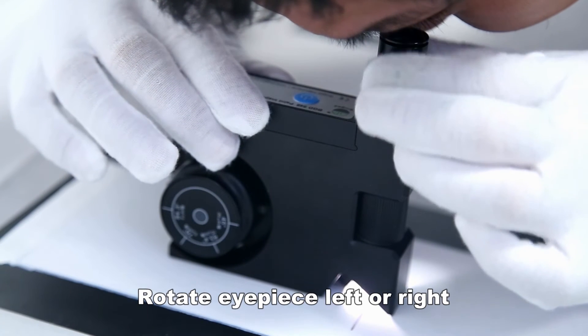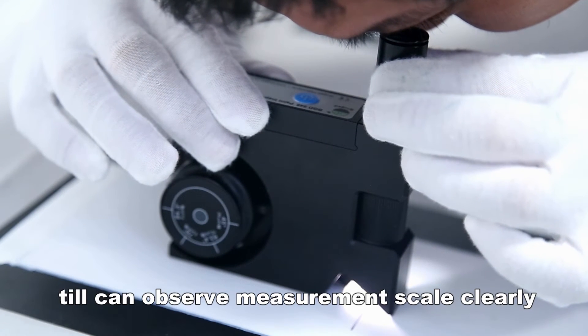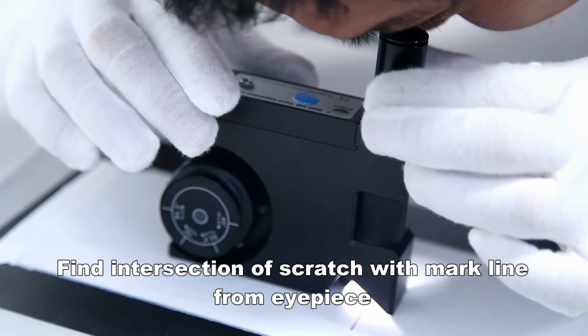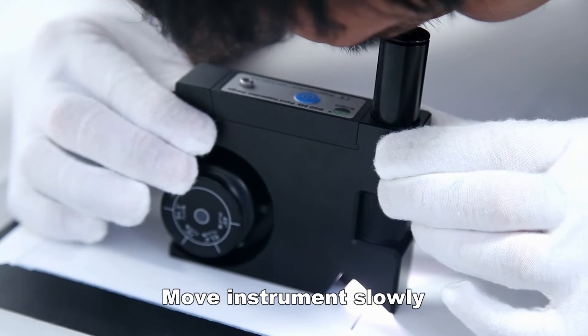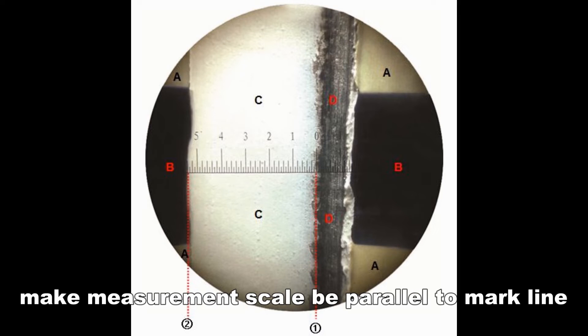Rotate the eyepiece left or right until you can observe the measurement scale clearly. Find the intersection of the scratch with the marked line from the eyepiece. Move the instrument slowly to make the measurement scale parallel to the marked line.